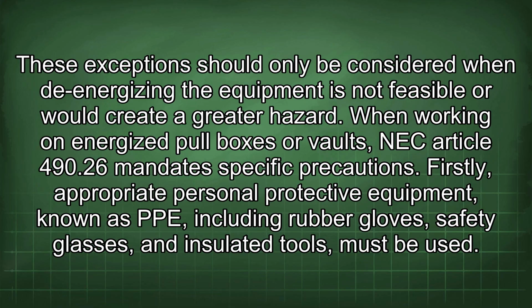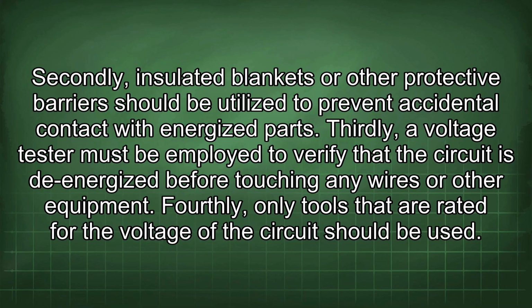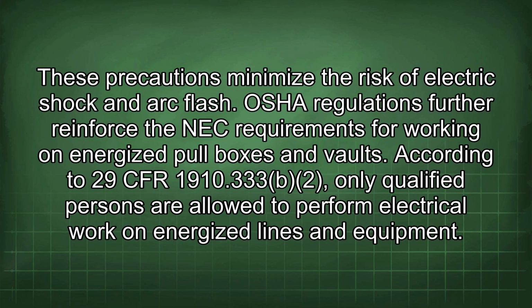When working on energized pull boxes or vaults, NEC Article 490.26 mandates specific precautions. Firstly, appropriate personal protective equipment, known as PPE, including rubber gloves, safety glasses, and insulated tools, must be used. Secondly, insulated blankets or other protective barriers should be utilized to prevent accidental contact with energized parts. Thirdly, a voltage tester must be employed to verify that the circuit is de-energized before touching any wires or other equipment. Fourthly, only tools that are rated for the voltage of the circuit should be used. These precautions minimize the risk of electric shock and arc flash.